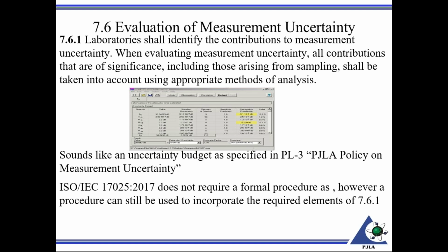For those accredited with PJLA, our policy on measurement uncertainty is PL3. If you look at PL3, it sounds a lot like a measurement uncertainty budget, which we have calibration labs prepare prior to getting accreditation, and review and change as things change. Before the standard was revised in 2017, a procedure was required. When the standard was revised in 2017, a formal procedure was no longer required. However, a procedure can still be used to incorporate the required elements specified in clause 7.6.1.